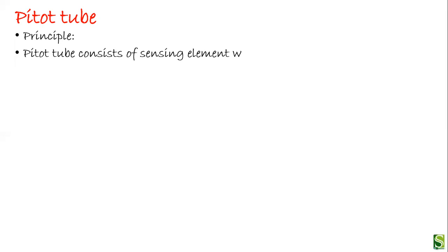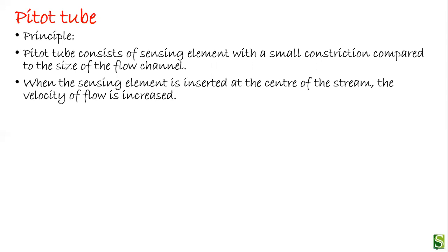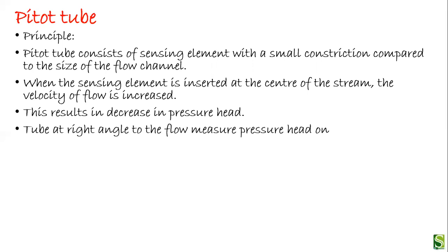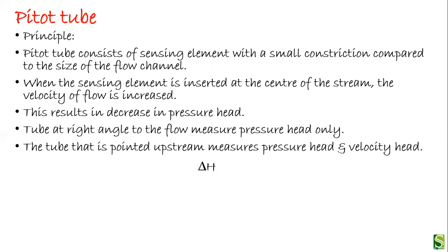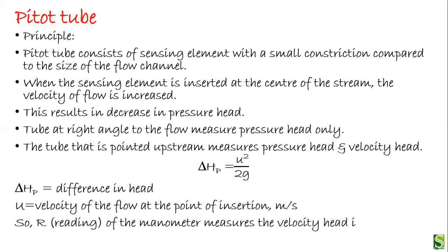Now we look at the pitot tube. Its principle: the pitot tube consists of a sensing element with a small constriction compared to the size of the flow channel. When the sensing element is inserted at the center of the stream, the velocity of the flow increases, resulting in a decrease in pressure head. The tube at right angles to the flow measures pressure head only, while the tube pointed upstream measures both pressure head and velocity head. The formula is: ΔHp = u²/(2g), where ΔHp is the difference in head and u is the velocity of flow at the point of insertion.